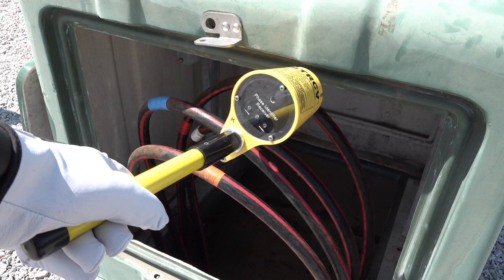As you may have noticed from the first set of tests we just conducted with the STRCV in the low current setting, we received no signal either direction. This may be possible since the red lead is connected to the concentric. There may be too many multiple paths to ground on the near end. In a situation such as this, we actually recommend connecting our CT clamp adapter to the STRCV so the current pulse pickup is much more sensitive.